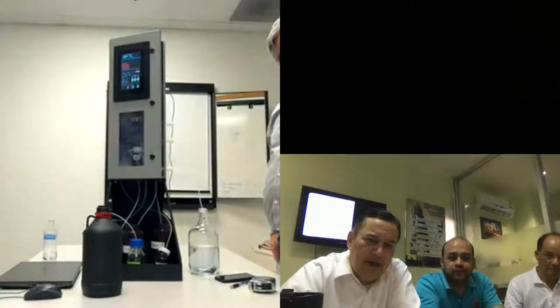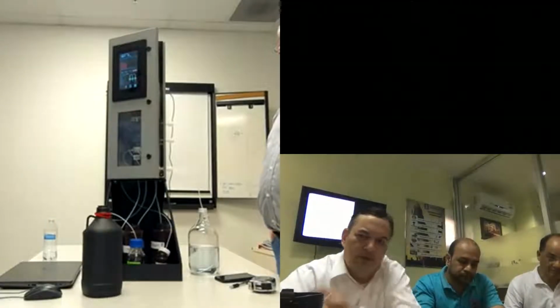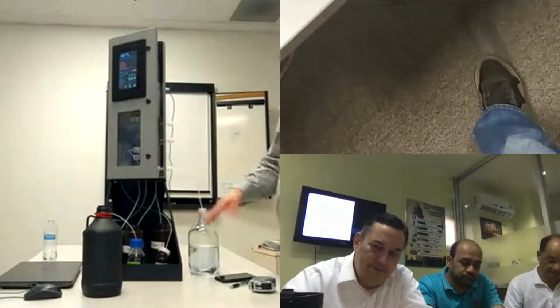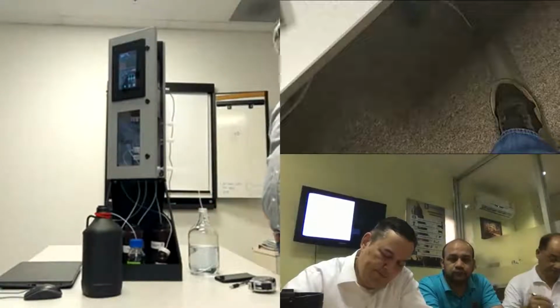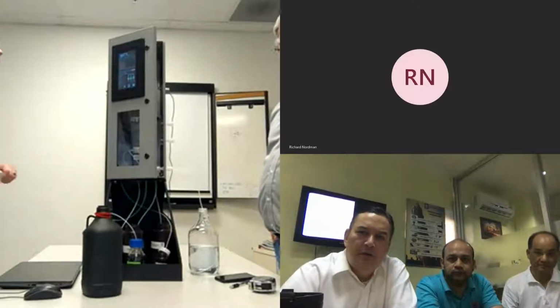Question: what's the temperature environment for this machine and the reagents? We're roughly—let me check—50°C max for sure. Minimum I can't remember off the top of my head, but we're above 0 for sure. In colder weather you have to worry about freezing of the reagents, since they typically have lower freezing points, but I can't remember the last time it froze here, so we're good.